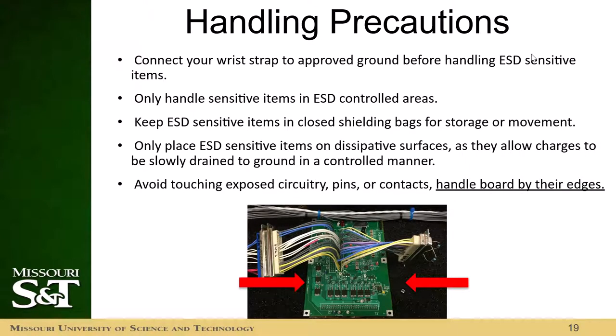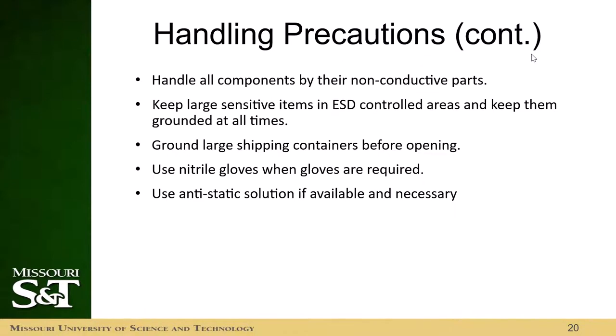Moving on to handling precautions. You'll want to handle ESD sensitive items in ESD controlled areas and keep them in shielded bags. Only put ESD sensitive items on dissipative surfaces. As shown in the picture, avoid touching exposed circuitry — if you have to handle something, handle it by the edges. Don't press your thumb down on top of the board as you might be causing things to connect that shouldn't be. Handle all components by the non-conductive parts. If you have large shipping containers, make sure they're grounded before you open them. The lab also provides nitrile gloves and anti-static solution if necessary.